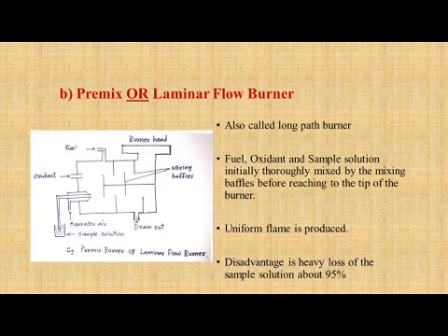This burner is also called a long path burner because fuel, oxidant and sample solution are initially thoroughly mixed in the burner before reaching the burner head, and that role is done by the mixing baffles. The fuel, sample solution and oxidant are thoroughly mixed, and the mist that forms reaches the burner head, and there is formation of a uniform flame.